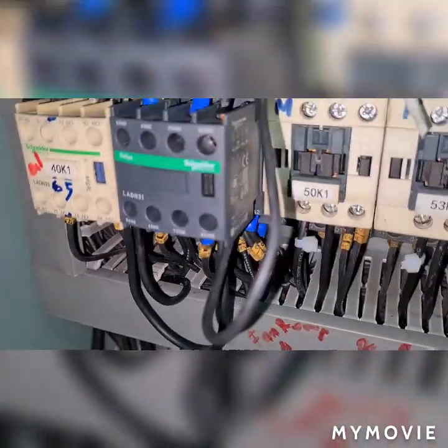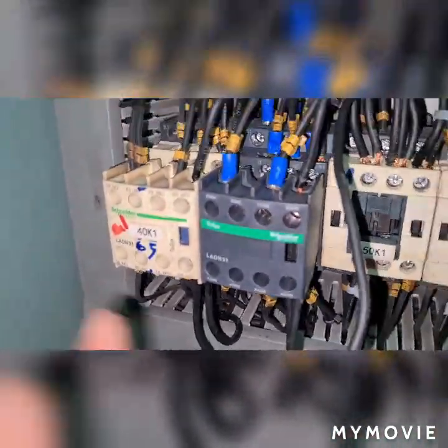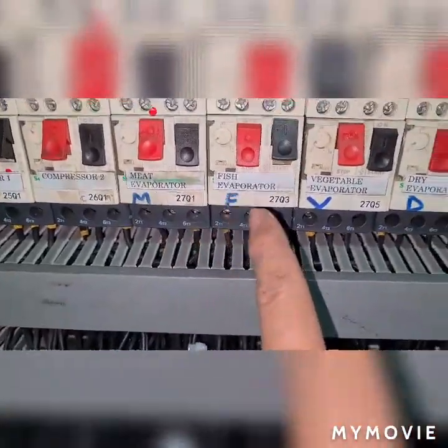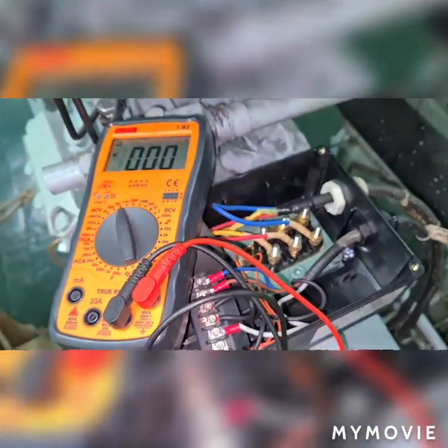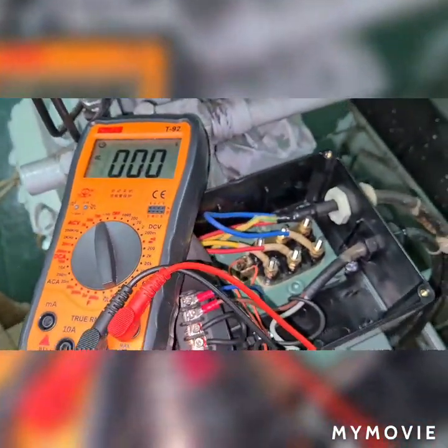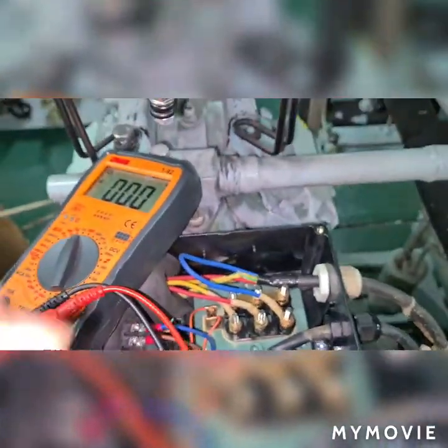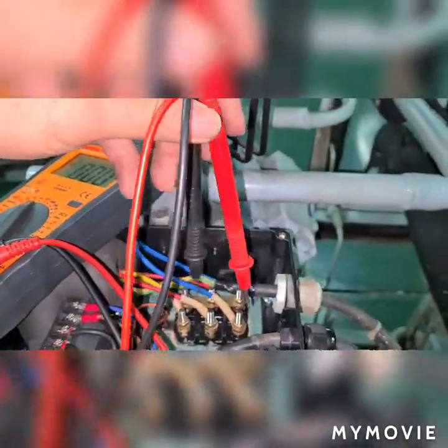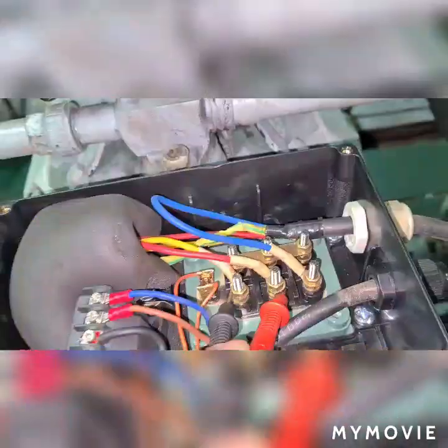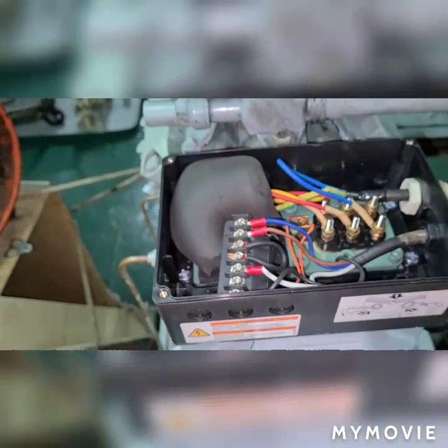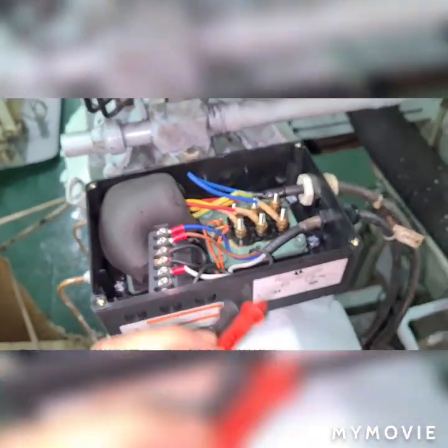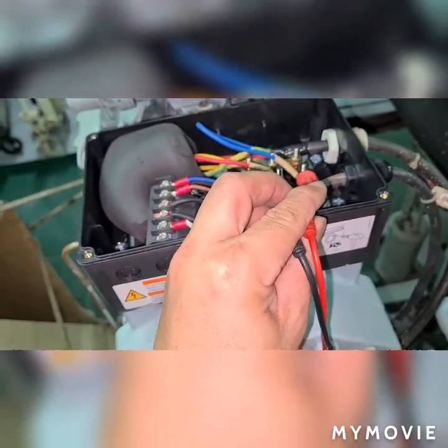and as you may notice, this is the compressor. This compressor, by the way, is a new one and newly installed, so I need to put this motor protector relay before the compressor will run, to operate it in a safe operation.